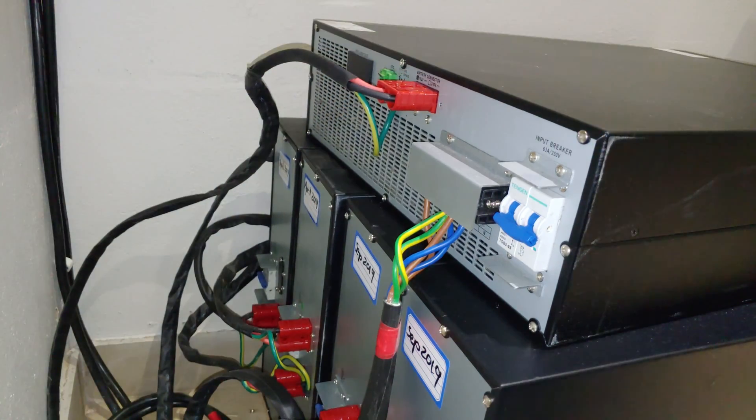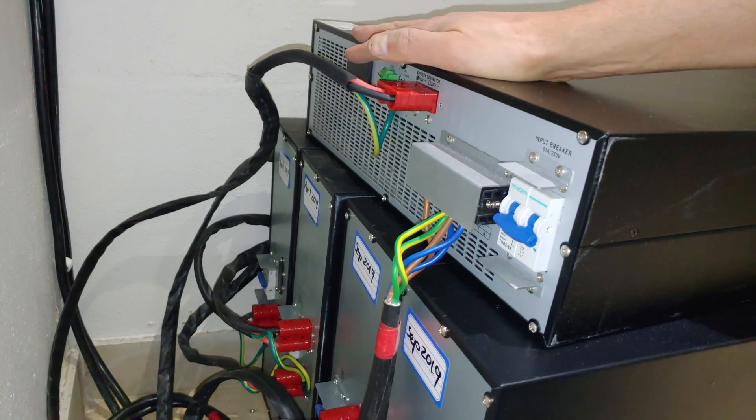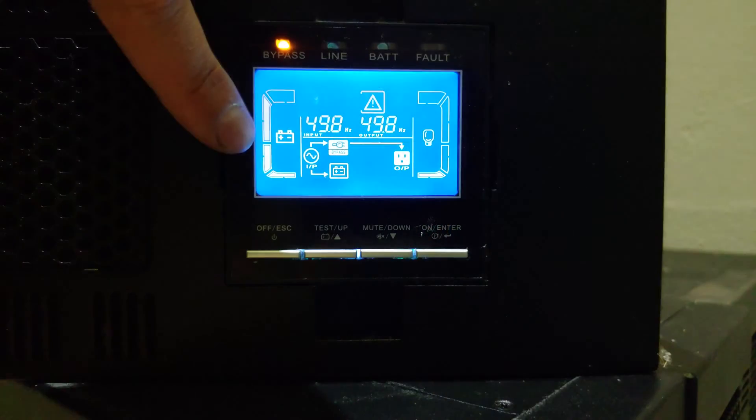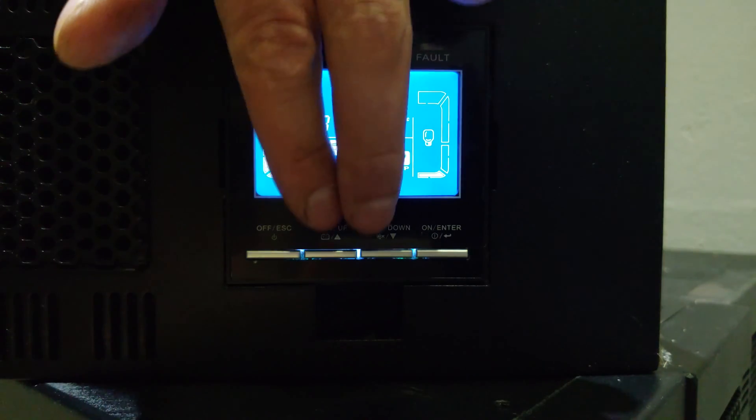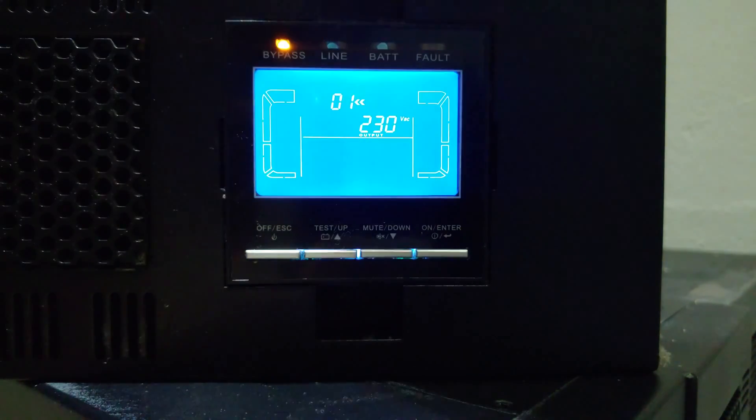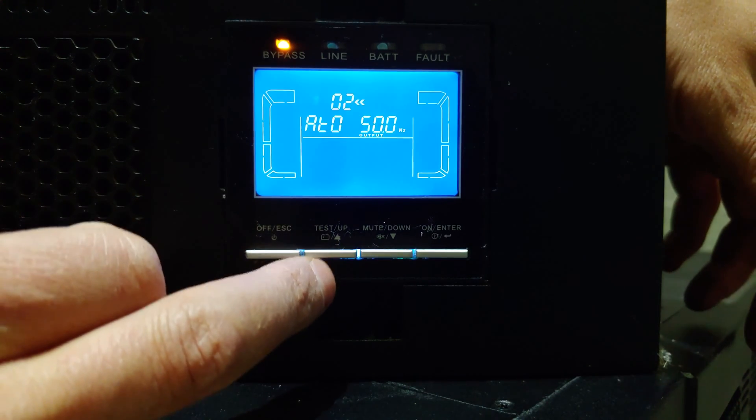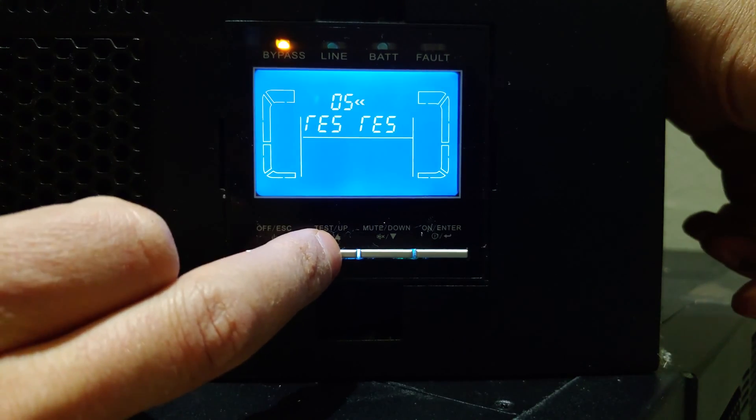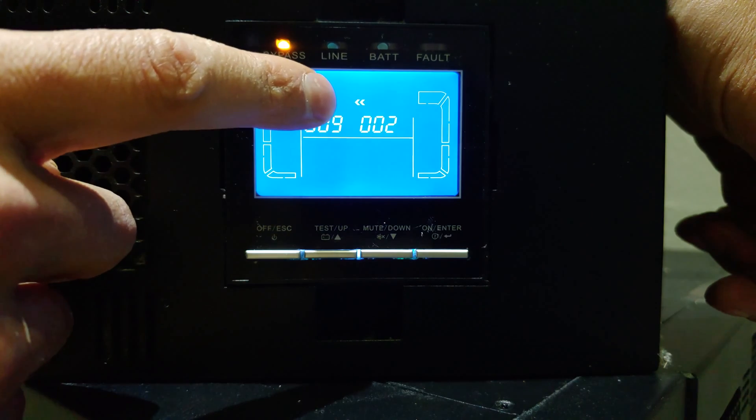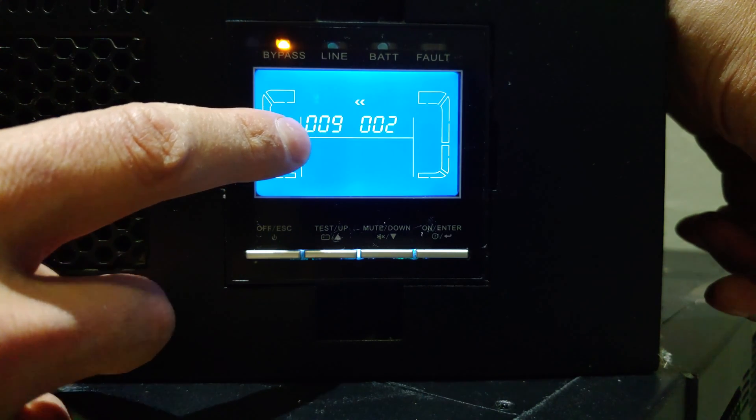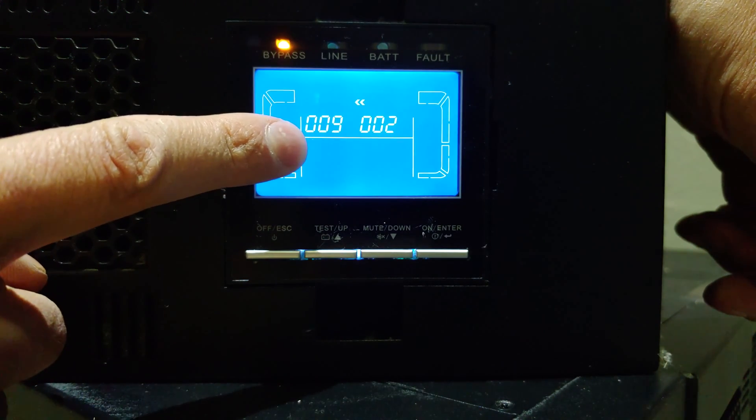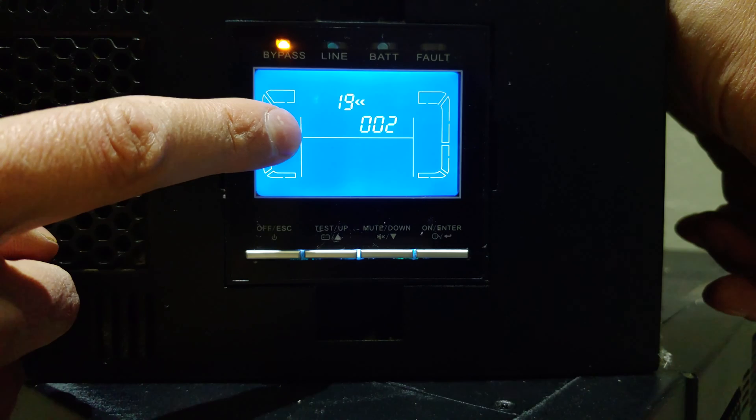Now all you need to do is tell the UPS how many battery banks you've got, and you might want to adjust the charging current. I'll show you how to do that now. All right, so what you want to do now is you want to tell it how many battery banks. So you press and hold these two buttons together and you see it goes into menu. You scroll through the menu. All right, so menu number 19—you can see that it's telling you how many battery banks you've got: two, and these are nine amp hour batteries.